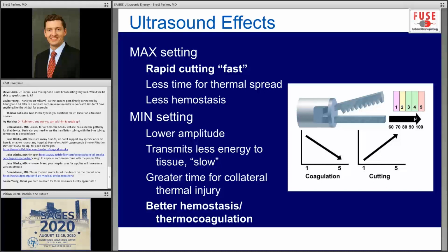Again, in reference to the question that was asked earlier about thermal spread, this ranges usually from 1.5 to 3 millimeters on the ultrasonic device, depending on which setting you use. So the min setting will have a higher range of normal, up to 3 millimeters of thermal spread, and the max setting would be closer to 1 reliably. And these user-dependent techniques that I've described can also affect the amount of collateral thermal injury, so are important to remember.